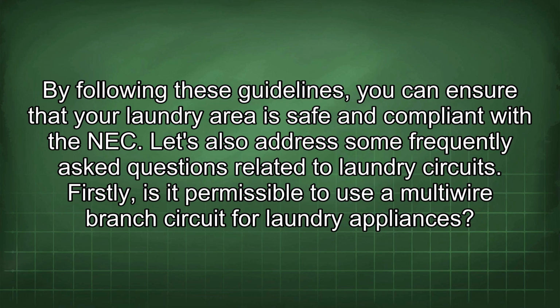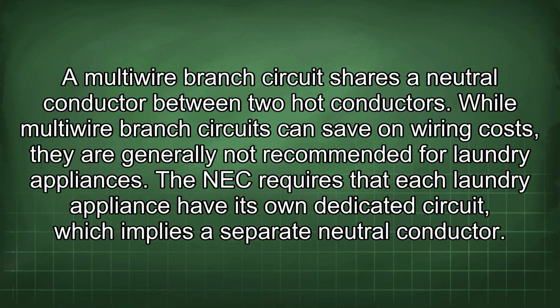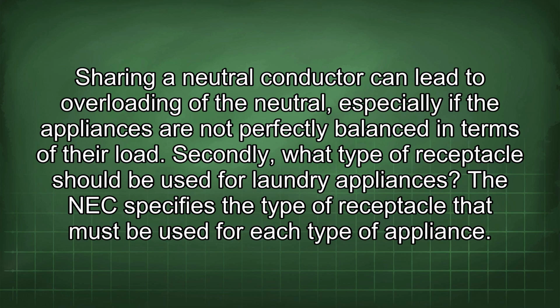Firstly, is it permissible to use a multi-wire branch circuit for laundry appliances? A multi-wire branch circuit shares a neutral conductor between two hot conductors. While multi-wire branch circuits can save on wiring costs, they are generally not recommended for laundry appliances. The NEC requires that each laundry appliance have its own dedicated circuit, which implies a separate neutral conductor. Sharing a neutral conductor can lead to overloading of the neutral, especially if the appliances are not perfectly balanced in terms of their load. Secondly, what type of receptacle should be used for laundry appliances?